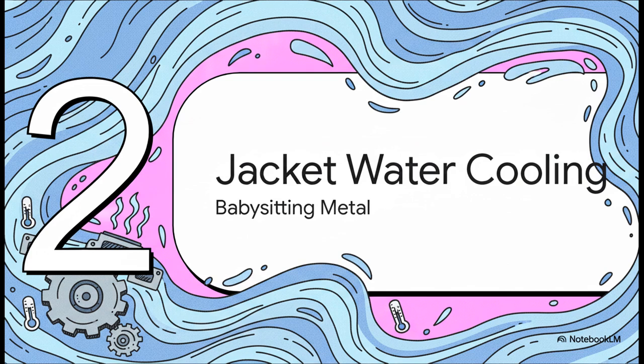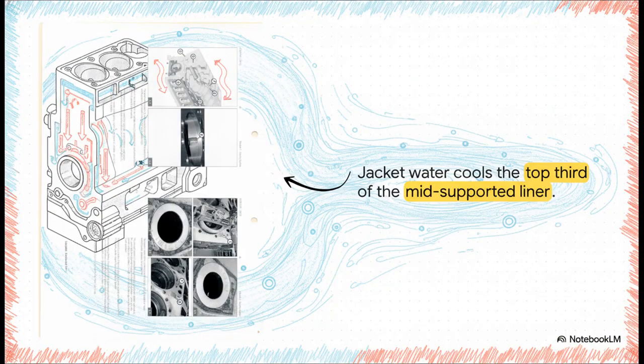Moving on to Section 2, jacket water, and how it essentially babysits the heavy metal of the engine. Following the flow path, the jacket water coolant passes through specific restriction orifices, and this is completely by design to maintain equal supply pressure to every single cylinder head. By routing coolant through the block and head structure twice in that dual-pass design, the system is actively babysitting the structural integrity of the combustion chamber. It's aggressively pulling away that intense heat from the top third of the mid-supported liner.